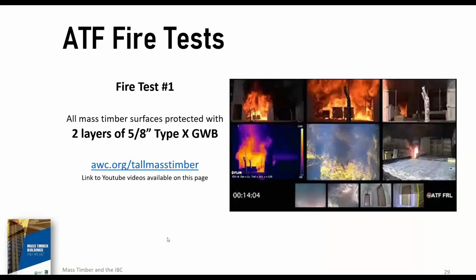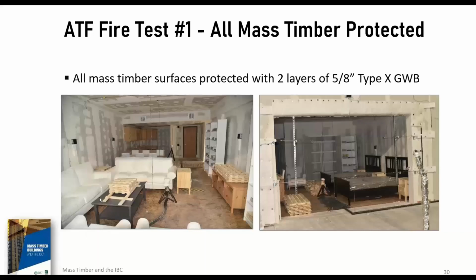So again, test number 1 is fully protected. Test number 2 is the exposed ceiling. Test number 3 is the exposed walls. Test number 4 is normal activation of 1 sprinkler head. And test number 5 is a forced delay of charging the standpipe to activate the entire sprinkler system in the test compartment. So what I'm going to do for you is some more still photos here.